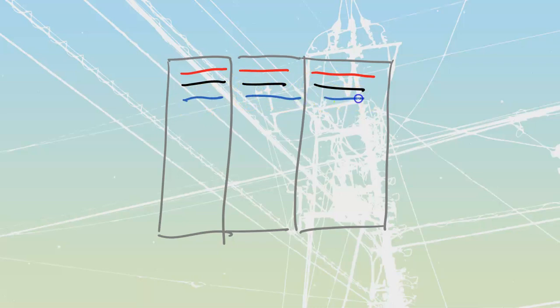And when I carry these things in to here, what I'm going to have to do once I've got them placed is make connections. So there's going to be specialized plates that come from the manufacturer that are going to span each of these gaps here to carry any sort of power that we need through our system itself. When I place these in, they're usually going to be done with a bolted type of connection that's just going to bolt through from one to the other.